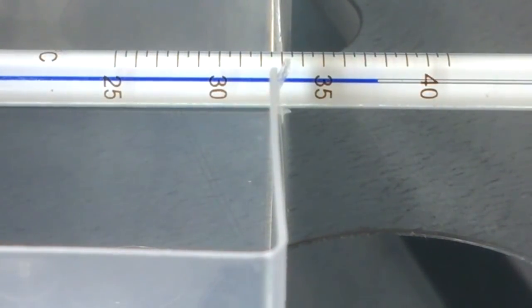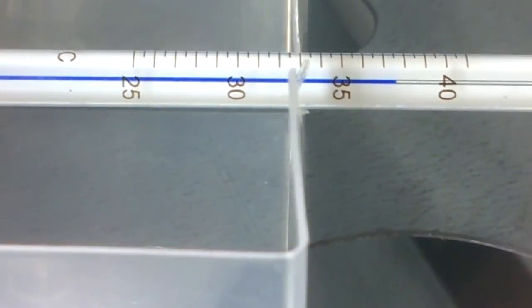So following a secondary calibration and having left the machine for half an hour, I've come back and I'm looking at it now, and there we are. It's spot on 37.5 on the glass thermometer that I've got in the machine, and if I move and look at what's going on, you can see that the spot check thermometer is saying 37.5 as well. 37.6 and 37, that is pretty much 37.5. So there we're certainly within 0.2 of a degree, and I think that's good enough for a calibration.